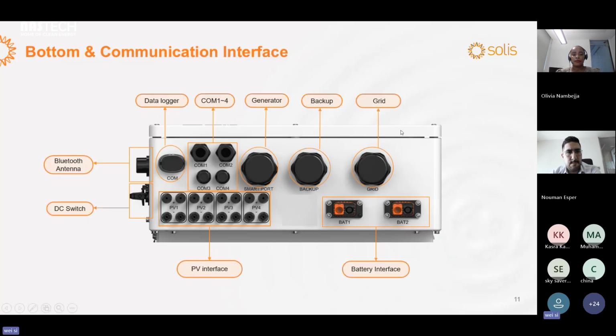Okay, it is very important for the installation. We can see the bottom of the inverter. On the left side, we have the Bluetooth antenna and DC switch. Here we can connect the PV panel. This COM port is designed for the local connection, and COM1, COM2, COM3, COM4 are used for communication cable connections, such as the meter, the CT, the DRM port, and other third-party controllers.